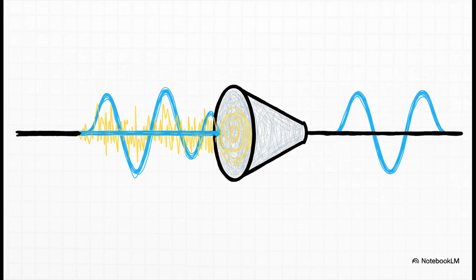Second, it's a power cleaner. All of our modern electronics can create this specific kind of electrical noise called third harmonics. This noise distorts the nice, clean sine wave our grid is supposed to have. The tertiary winding acts like a specialized filter, almost like noise-canceling headphones for the grid, trapping these harmonics and letting them circulate harmlessly, which keeps our power supply clean and protects all our sensitive gear.